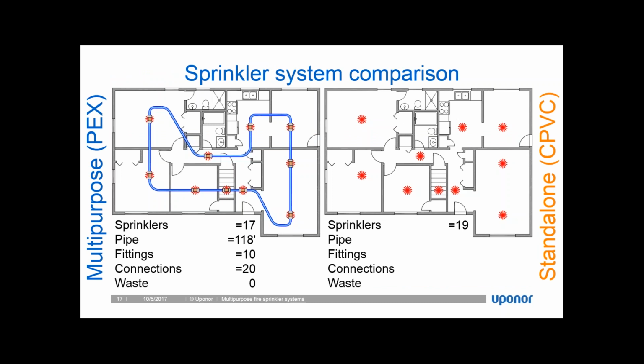On the CPVC side, things look a little bit different because CPVC is a rigid piping system. So anytime I need to make a turn with the pipe, I have to install a fitting. When I look at the CPVC side-by-side comparison, I can see elbows where I need to turn and pick up sprinklers. Now this is why, actually, larger pipes are usually required for standalone systems. I don't have the benefit of having water delivered to the sprinkler from 2 points. I'm either going to have the water come in on one side of the building or the other side of the building and pick up all of these branch lines.